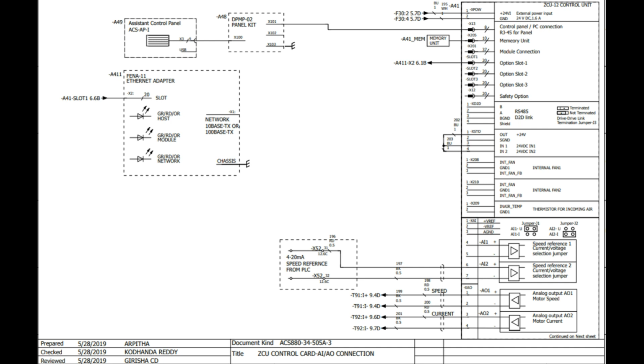XSTO, that is safe torque off, what you can see here. And here you can see the connection is between 1, 2, 3 and 4. Earlier in ACS 800 or 850 you have seen the connection between 1 to 3 and 2 to 4. So there is some change here, that 24 volt is directly given from 1 to 3 and 4. Next, these are default connections. We will skip them and come directly to the bottom part, where we have to see the reference, how the reference is given and how the feedback goes back to the PLC. So the very first thing is XAI, that is the XAI slot, and here we will directly go for channel number 6 and 7, that is analog input 2.